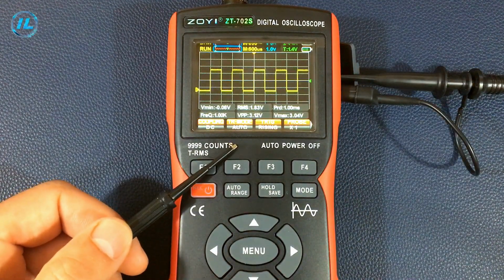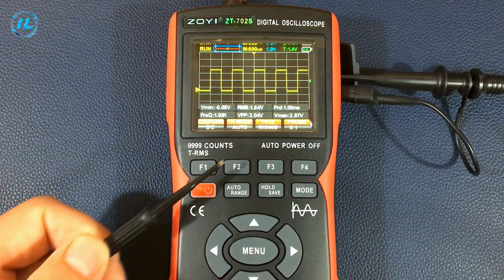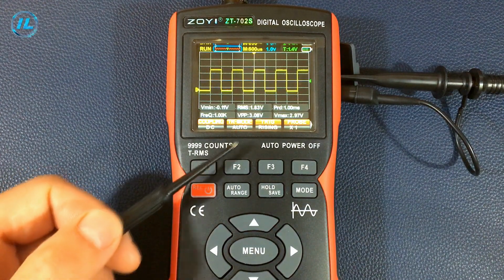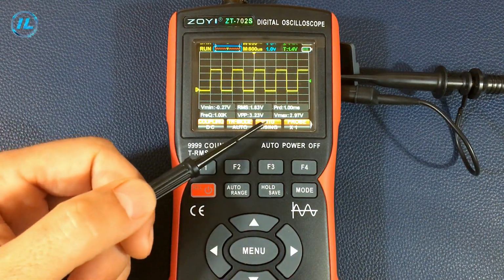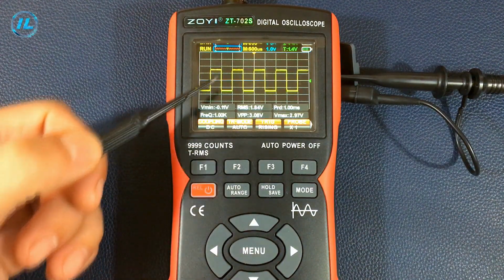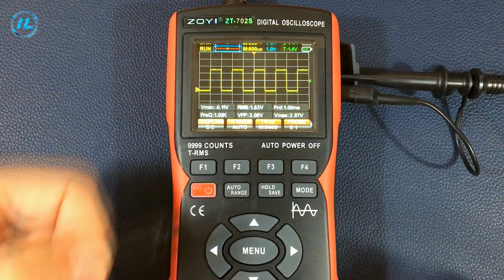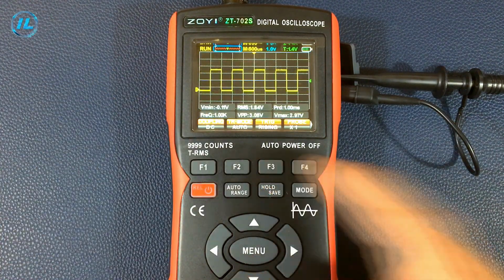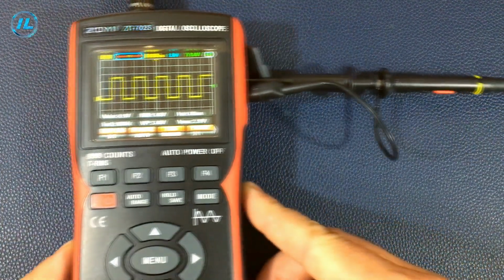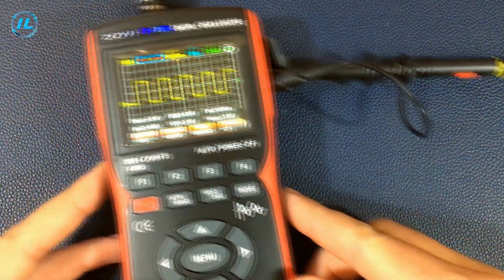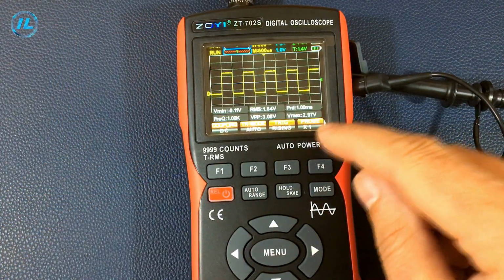The next item is the scan mode. The automatic mode is now set. You can also choose manual mode and single mode. Next is the trigger. The waveform will be shown on an ascending or descending front. The next item is the divider. When you turn on the divider, you need not only to shift the switch on the oscilloscope probe, but also to change the value programmatically.